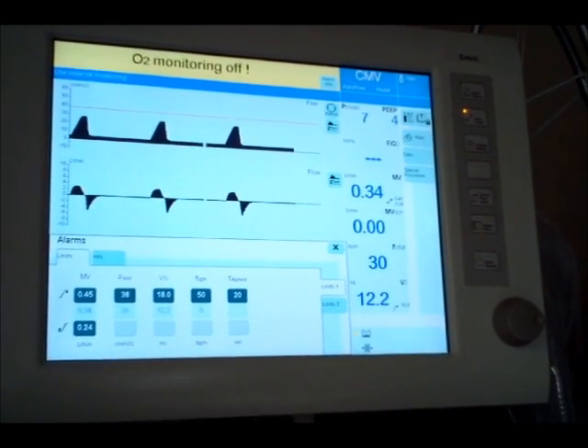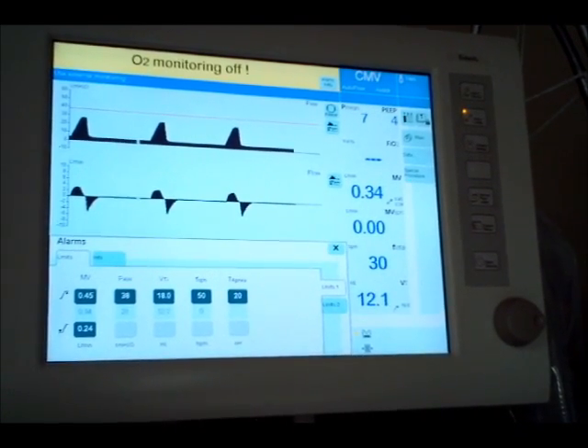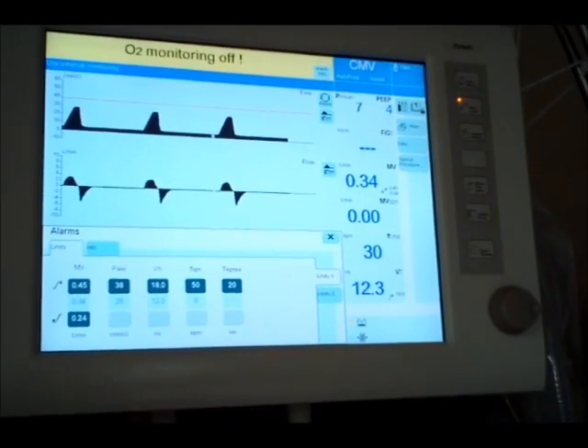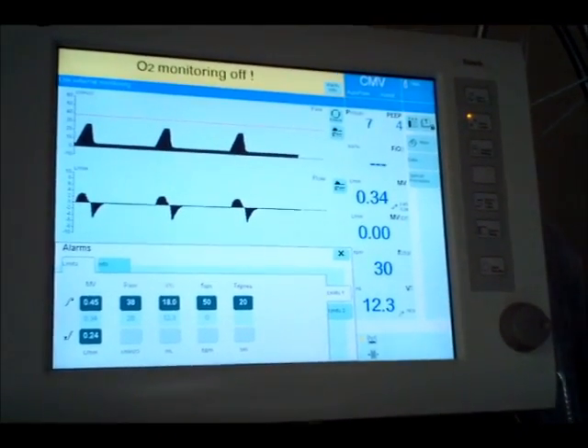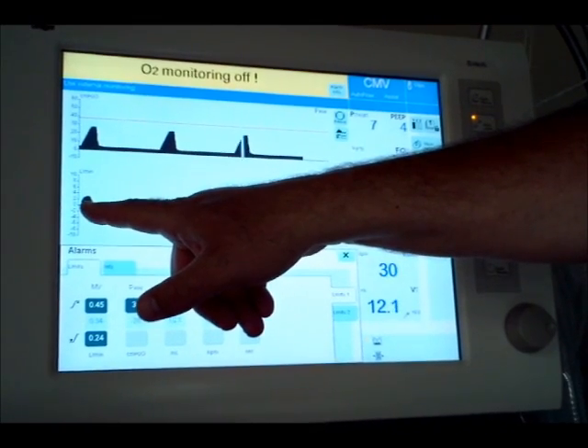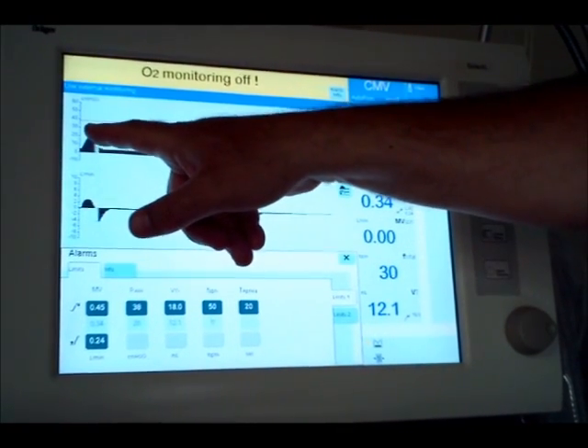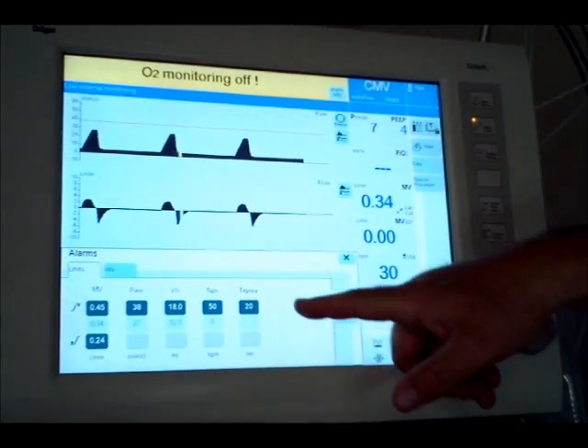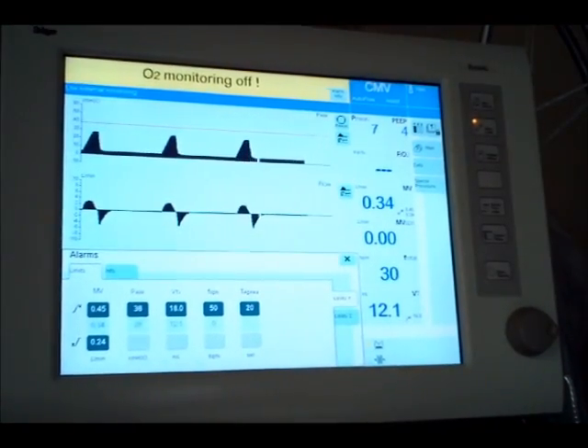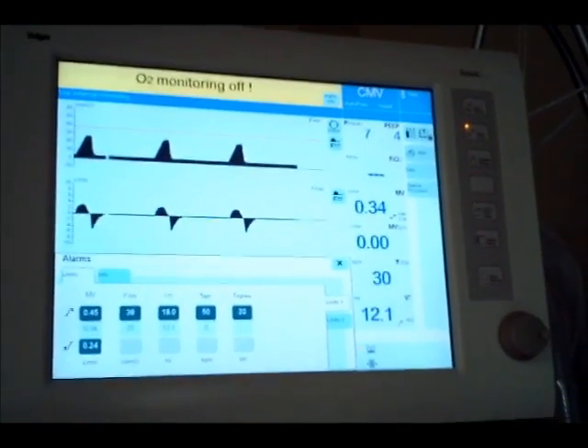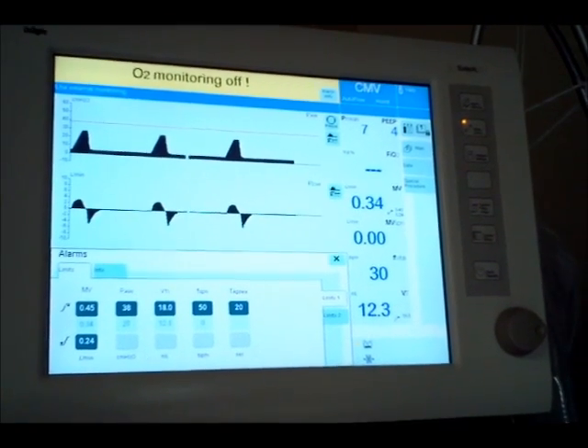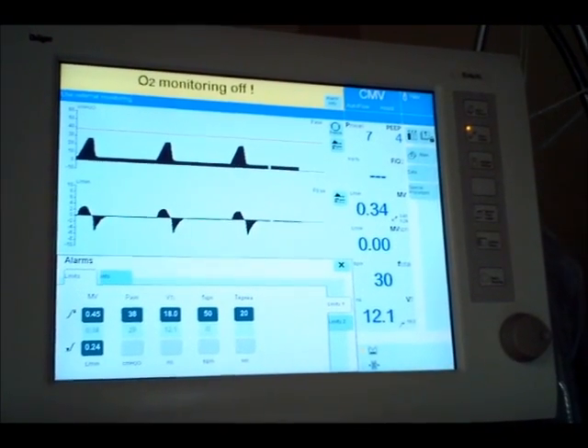XL? Remember, we set an inspiratory flow on the baby log. This does all the flow for you. In other words, it's doing a lot of math, so it's figuring here's your inspiratory flow curve. What flow do I need to get this pressure in 0.25 seconds, or whatever my slope is, into the inspiratory time. So it's just updating breath to breath to breath to breath and adjusts.